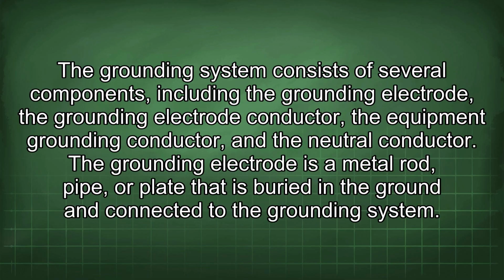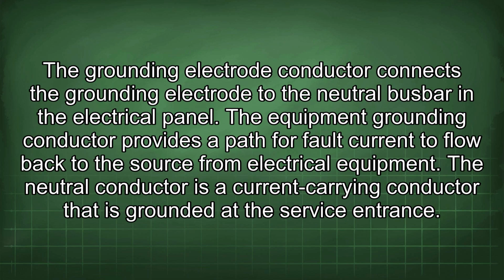The grounding system consists of several components, including the grounding electrode, the grounding electrode conductor, the equipment grounding conductor, and the neutral conductor. The grounding electrode is a metal rod, pipe, or plate that is buried in the ground and connected to the grounding system. The grounding electrode conductor connects the grounding electrode to the neutral busbar in the electrical panel. The equipment grounding conductor provides a path for fault current to flow back to the source from electrical equipment. The neutral conductor is a current-carrying conductor that is grounded at the service entrance.